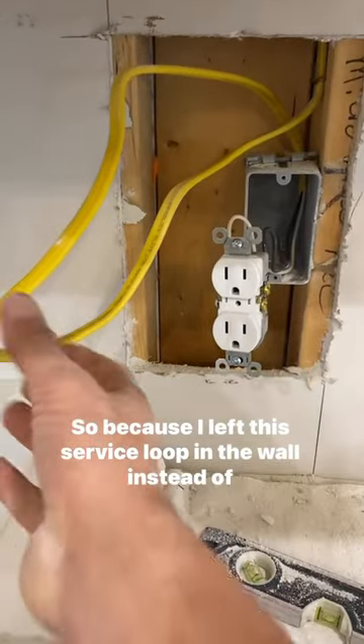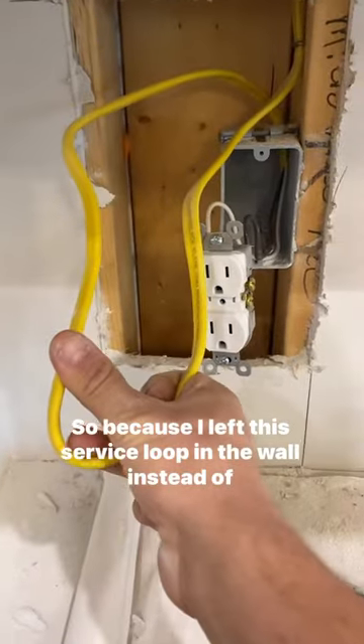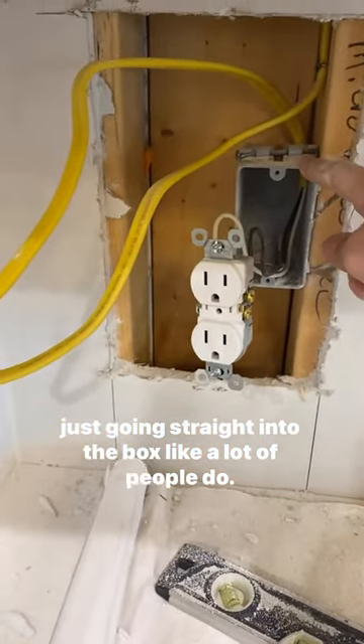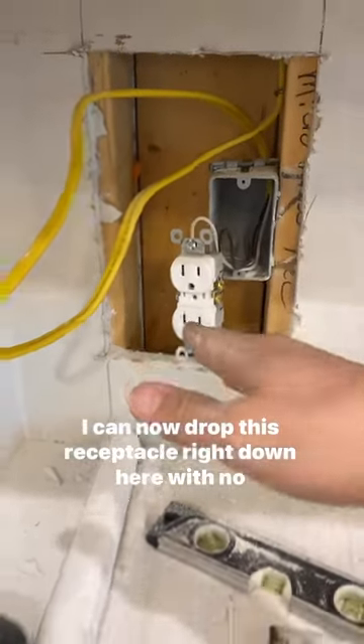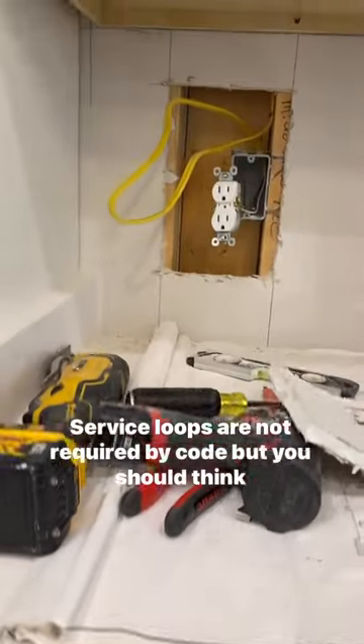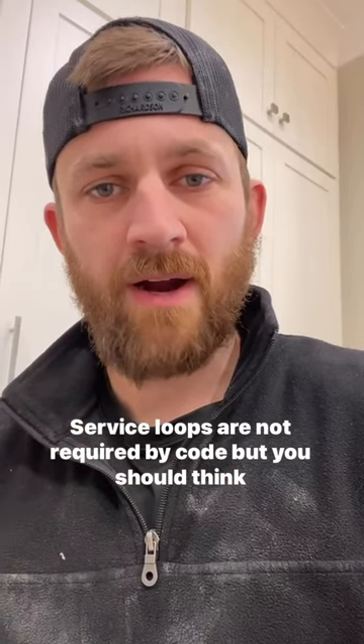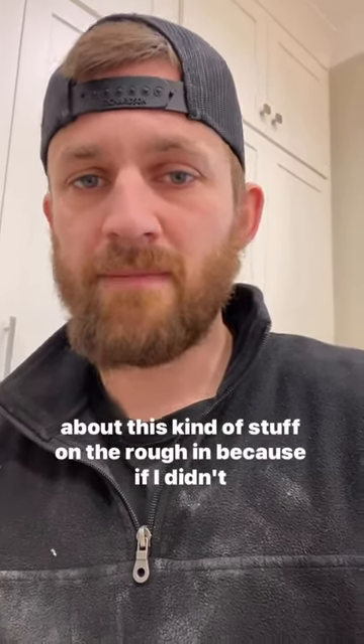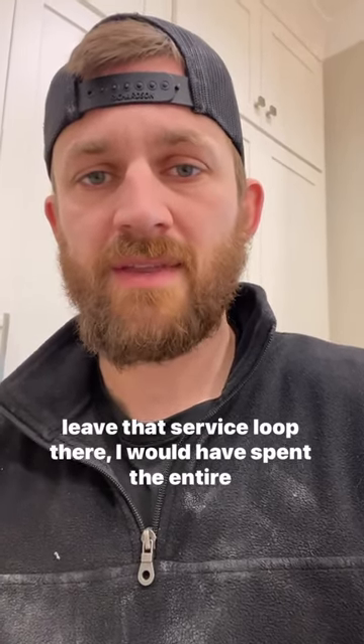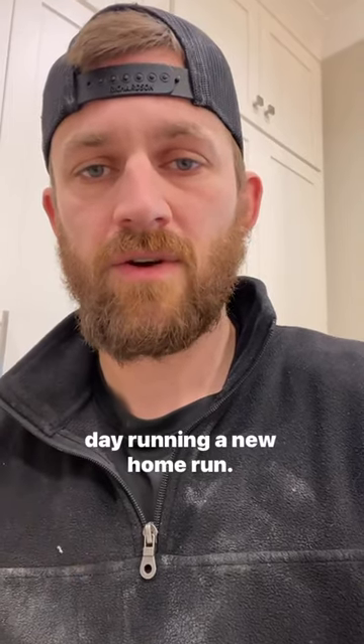Because I left a service loop in the wall instead of just going straight into the box like a lot of people do, I can now drop this receptacle right down here with no issues. Service loops are not required by code, but you should think about this kind of stuff on the rough in — because if I didn't leave that service loop, I would have spent the entire day running a new home run.